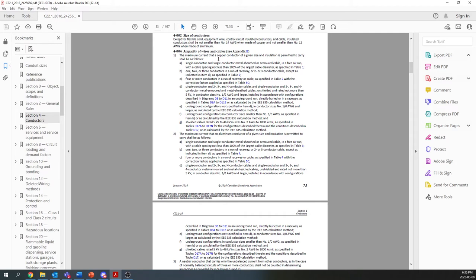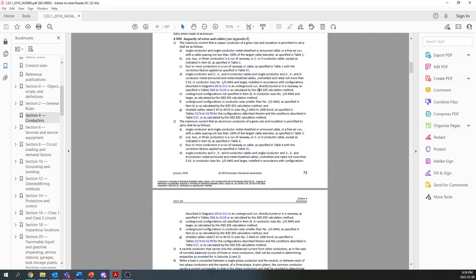That doesn't happen anymore because aluminum wire is rarely, if ever, used in small wiring in buildings. It's most often used in big feeders, where the devices that you're terminating that wire into are actually rated for aluminum wiring. So it's very safe if you're using the proper alloy. And the other thing is new aluminum alloys have been developed in the years since the 1970s. That, in large part, as well as the proper device ratings, have allowed the safe use of aluminum conductors nowadays. So essentially, these rules are copied in large part for aluminum and for copper.